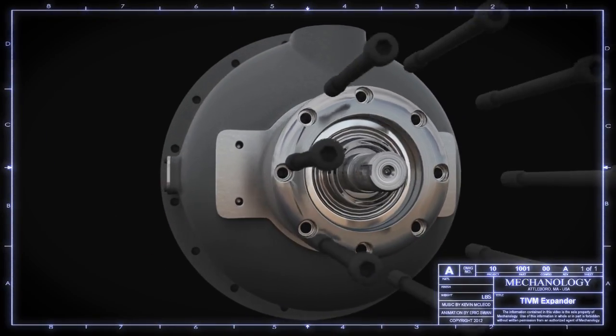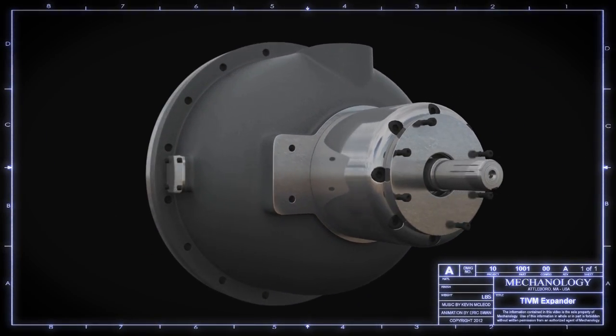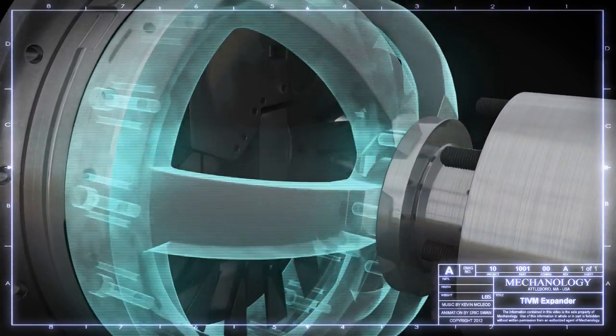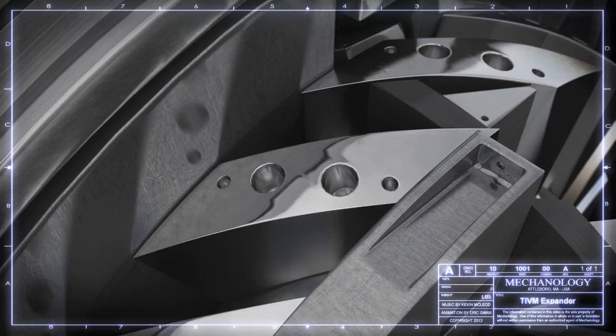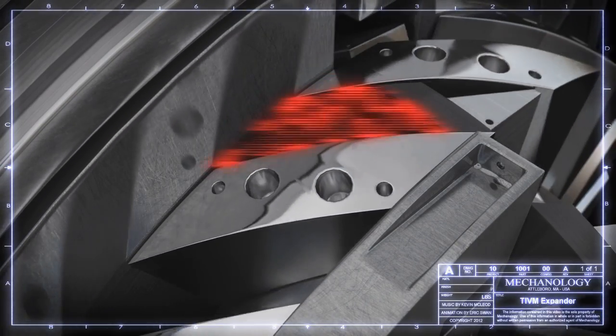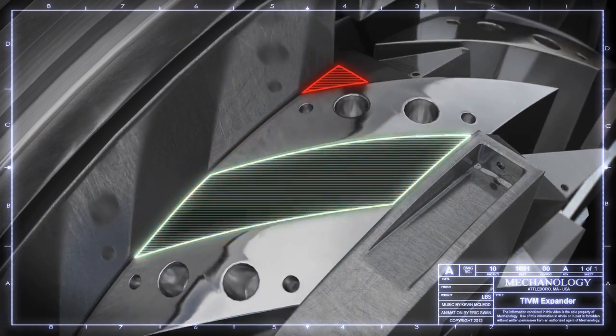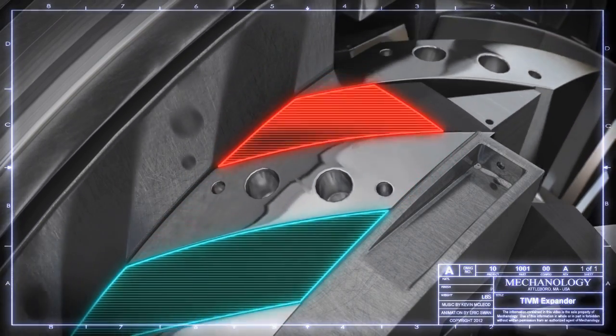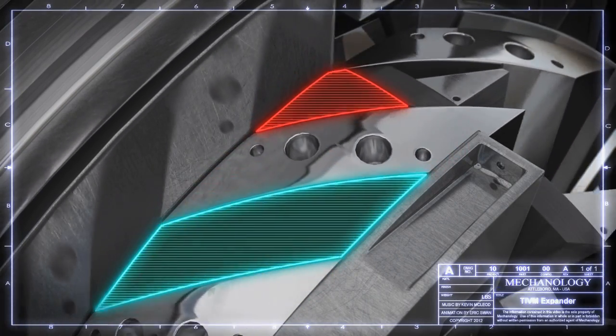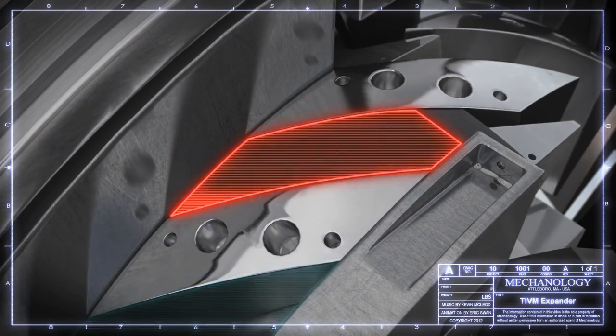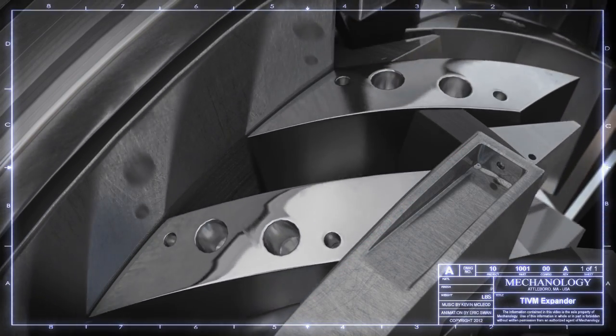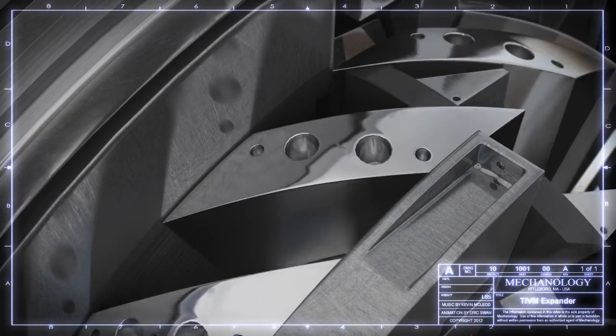Now we get a chance to peer inside the TIVM. As the animation shows, the volume of each successive expansion chamber grows from small to large. The high-pressure steam, shown in red, enters through the inlet port and expands with the growing volume of each expansion chamber. As the steam expands to a lower pressure in one chamber, a new charge of high-pressure steam is entering the following chamber. This is what allows the TIVM to be self-started from a dead stop by simply supplying pressurized steam to the inlet port.